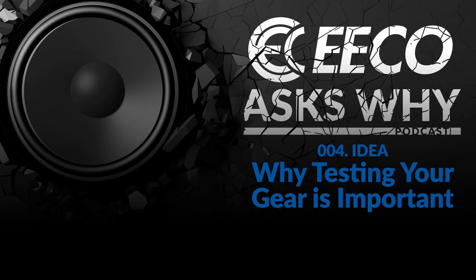Yeah, absolutely. What's critical to me if I'm a building owner with new equipment in it? I want to make sure that the contractors that installed my equipment installed it properly per code. I want to make sure that they've applied proper torque to all of my electrical connections. I want to make sure that there are no issues with any of the cables and wires that they ran. And I want to make sure that the manufacturer built the equipment properly and that the breakers are working. Okay? That seems like a lot to ask for, but honestly, that's my bare minimum expectation if I was going to be buying new equipment. I want the contractor to be qualified to do good work, and I want the OEM equipment to be in the highest quality standards that exist.